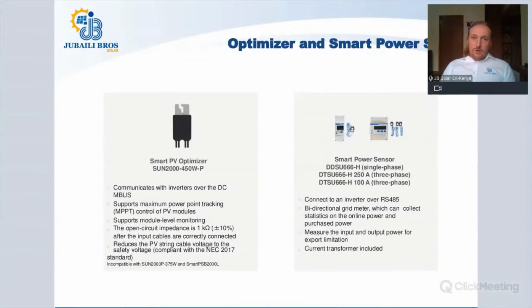In many regions across the world, you're not allowed to feed your solar energy back into the grid. This power meter is compatible with the Huawei inverter and allows you to set export limitation settings, whether that's zero export or another limit. If you're in a region that requires zero export to the grid, you'll need this product to prevent solar energy feeding back into the grid.